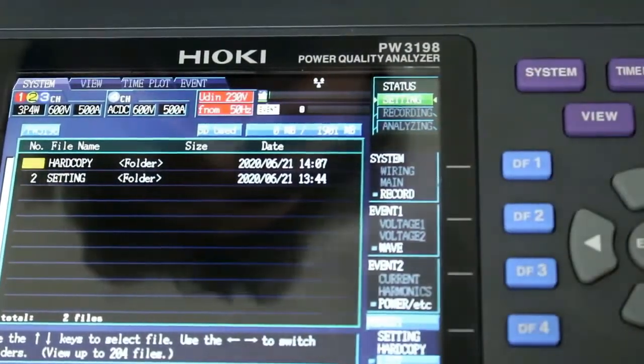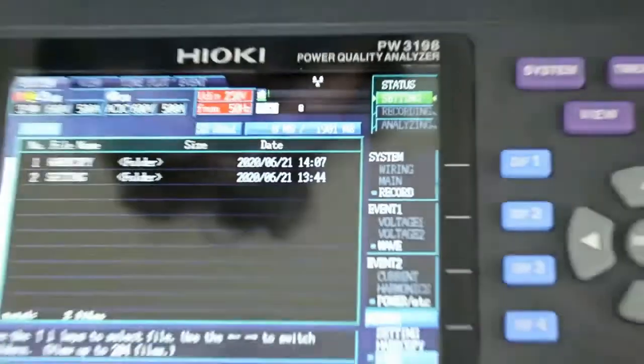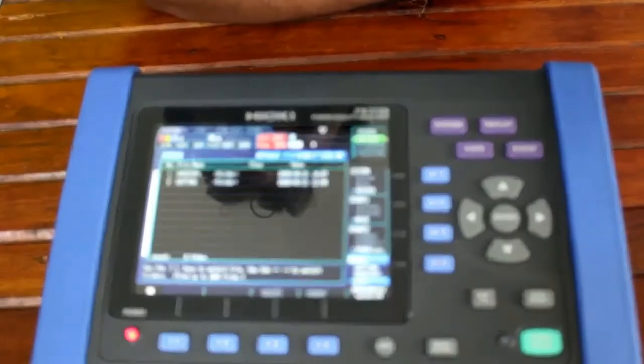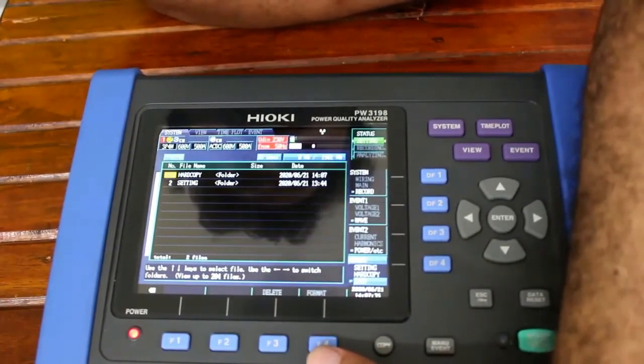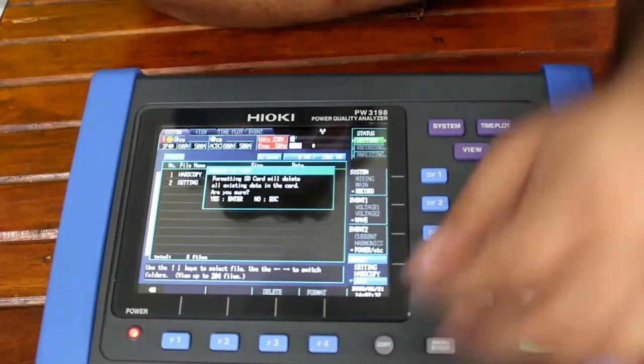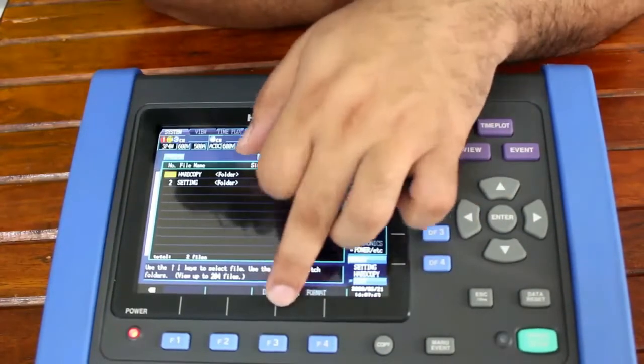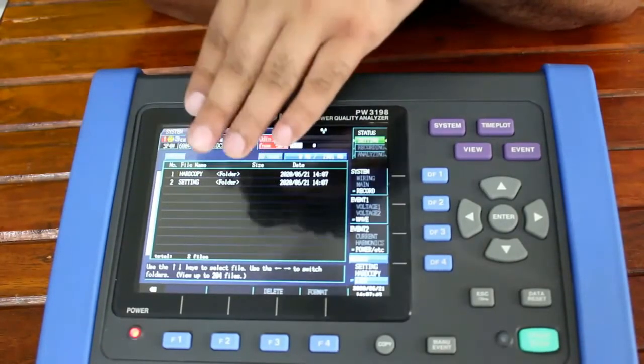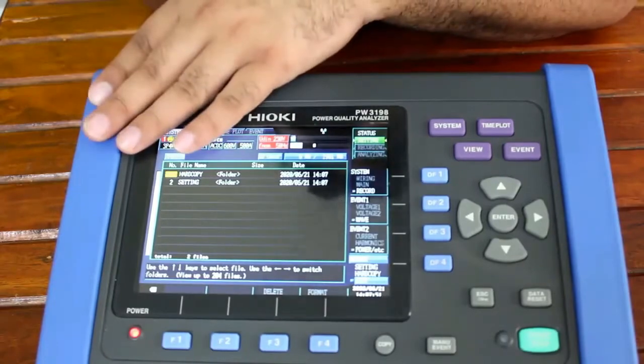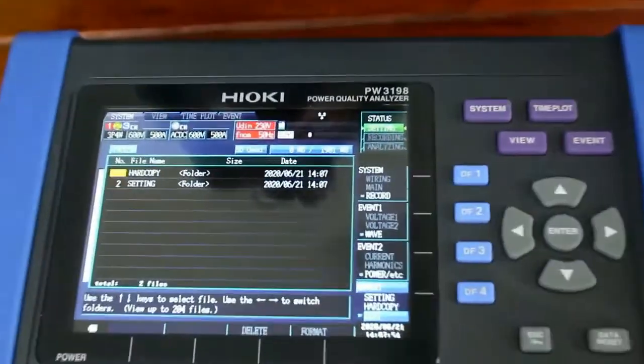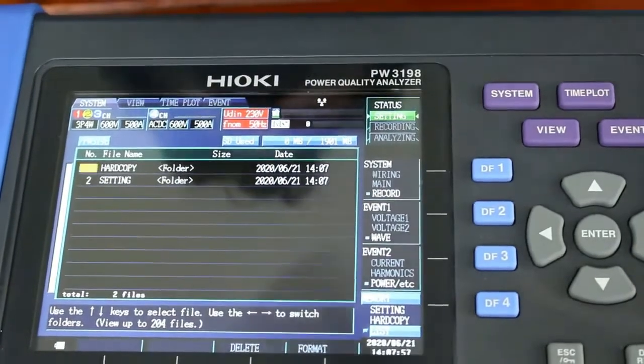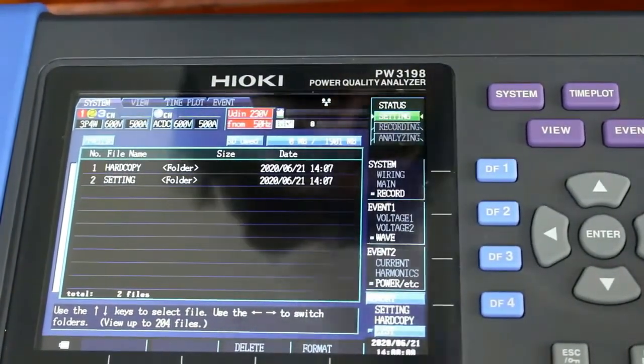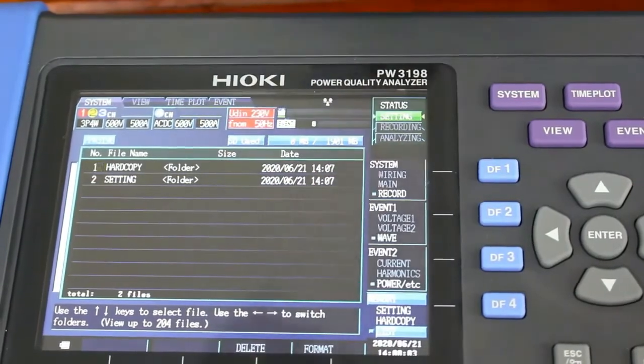Now if anything is there, you can format it from here. If you want to format the SD card, you can press F4 like this, then press enter and it will format the SD card, or you can select and delete it. One thing please note: do not format the card from your computer or system. Please format the card from the power quality analyzer only, as this analyzer's SD card has its own system files.